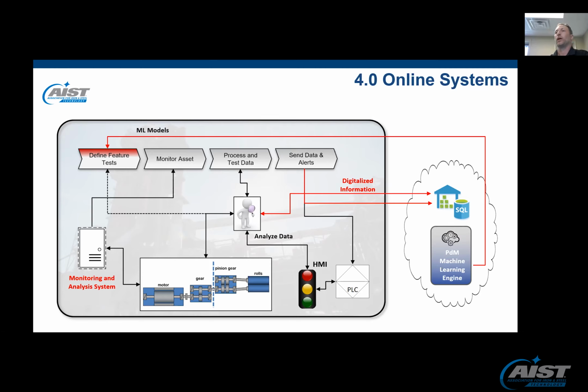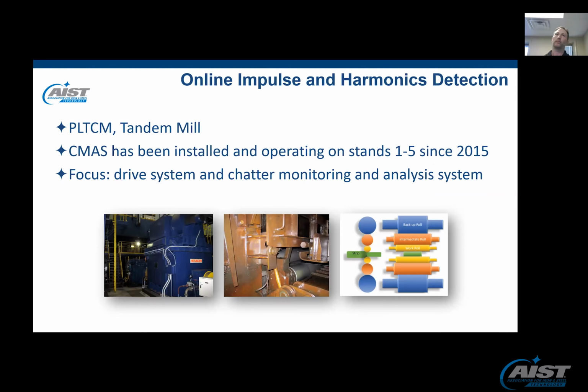At that point, we're able to develop the machine learning models we were talking about. Those models can then move back to the machine and actually be implemented into the condition monitoring system. And if you notice, we changed the name of the system from a monitoring system or CMS to a condition monitoring and analysis system, because we've actually pushed the analytics to the edge device. And this feedback loop is something that goes on and on for the life of the machine, the asset, and the system.